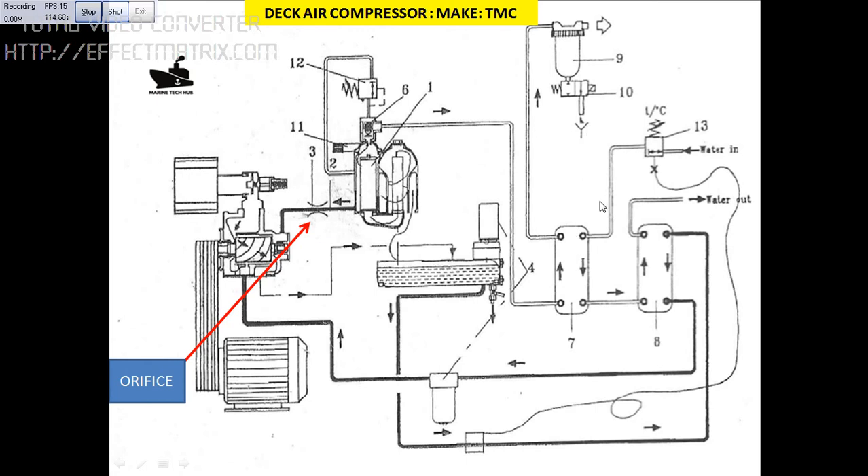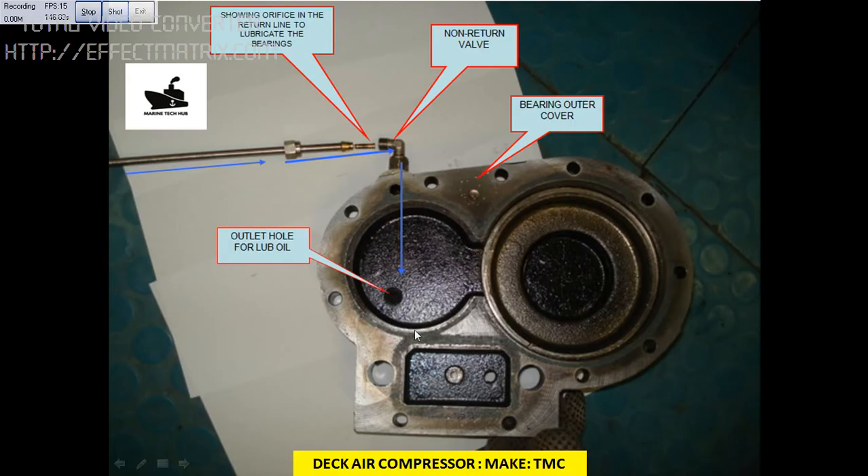You can see the water, and these are the filters here, and these are safety valves. The main concern here is to make sure that the temperature of the compressor running should be above 80 or 90 degrees. Why? Because of the humidity in the air, there is always a possibility that water can come into the oil, so you have to make sure your sump oil is not contaminated by water.